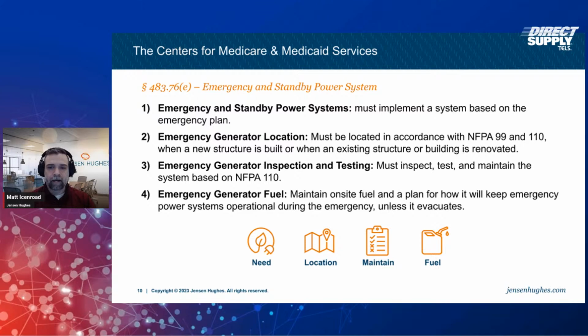We'll talk about lithium batteries in a moment, or if you're having a vendor deliver fuel. It's important to note that the regulation specifically mentions that there is no delay in fuel consumption. So if you run out of fuel and you're going to have a delivery, there cannot be a delay between the generator going offline and new fuel being delivered. They have to happen almost at the same time, which will be challenging, so keep an eye on that.